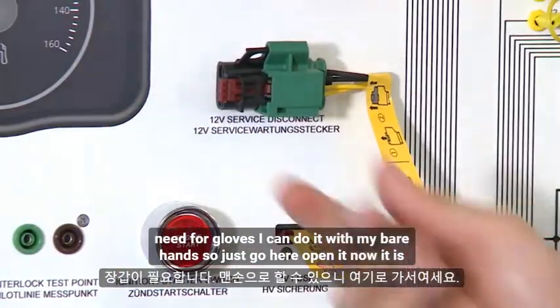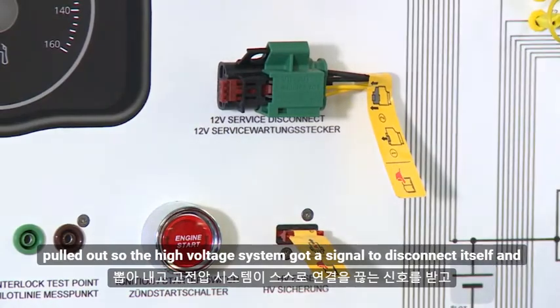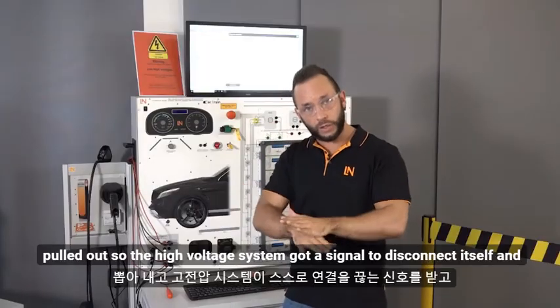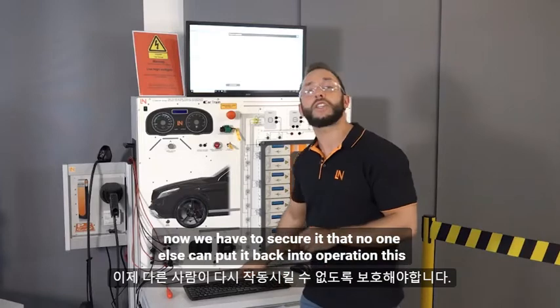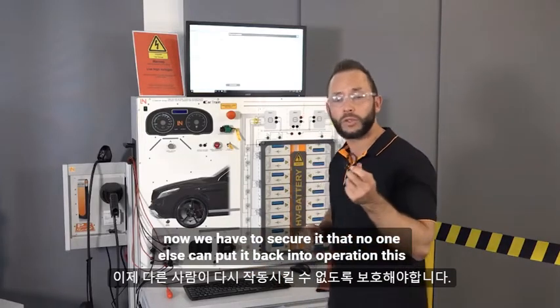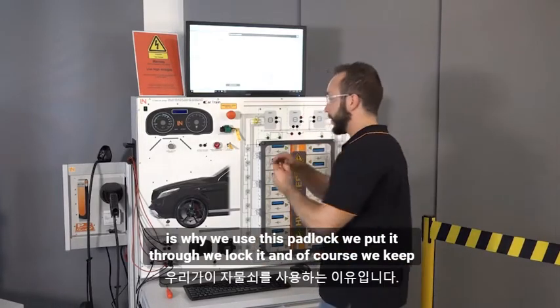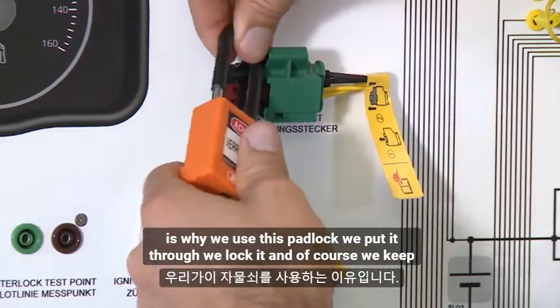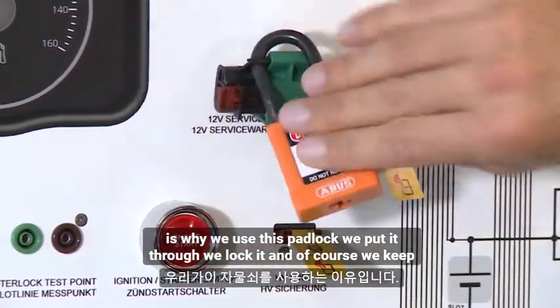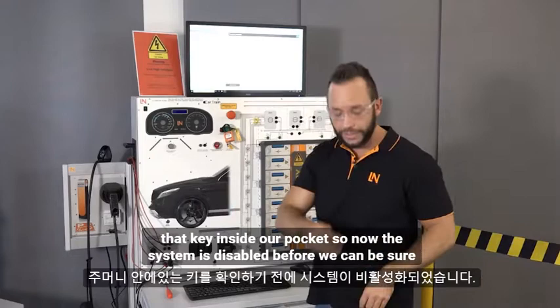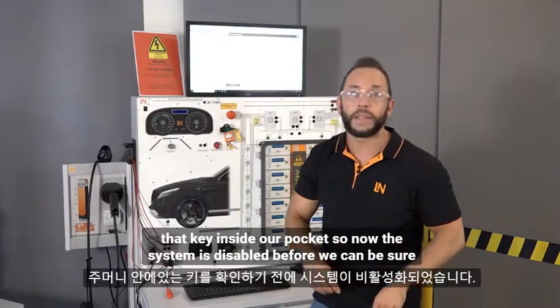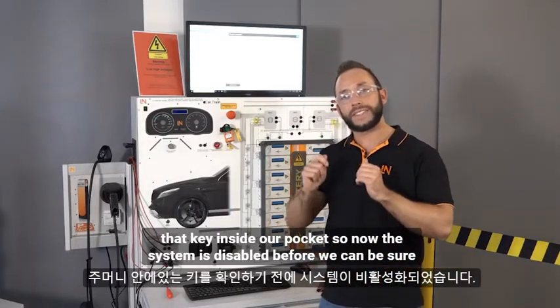So just go here, open it. Now it is pulled out, so the high voltage system got a signal to disconnect itself, and now we have to secure it so that no one else can put it back into operation. This is why we use this padlock. We put it through the hole, we lock it, and of course we keep that key inside our pocket. So now the system is disabled.